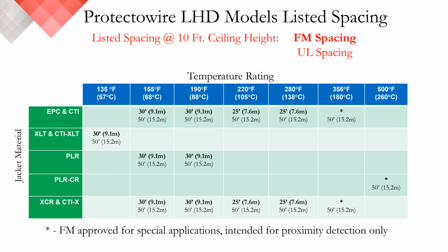This chart shows each detector's FM approved and UL listed spacing for each of the Protectowire linear heat detectors. Note that Type 356 and 500 don't have an approved spacing per FM or UL. They are listed per FM for special proximity detection applications only. Examples of this would include conveyors, fixed or floating roof tanks, kitchen hoods, things of that nature.